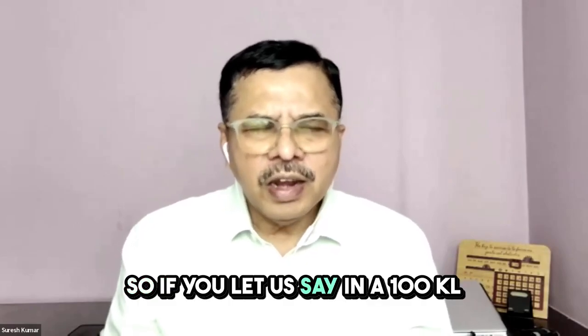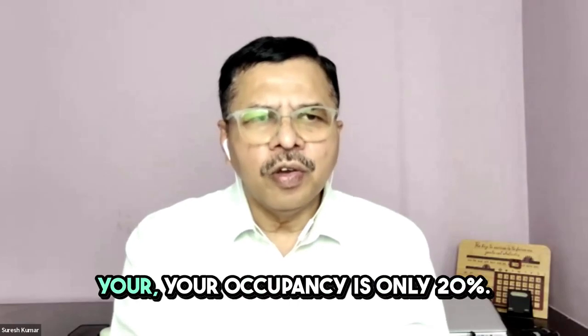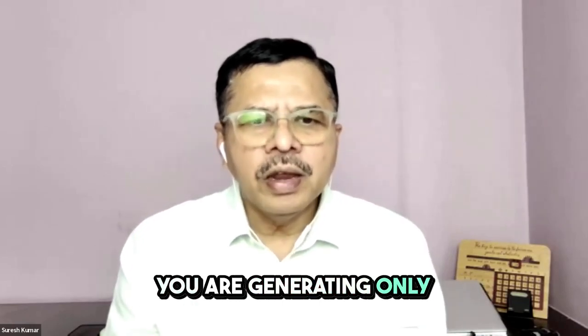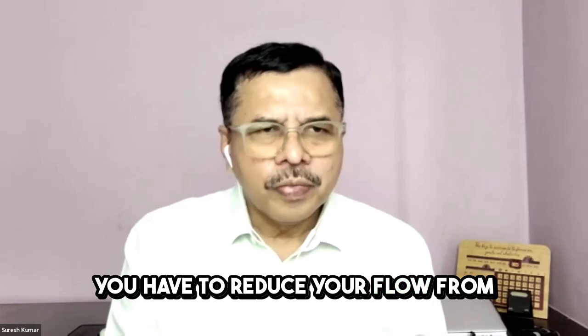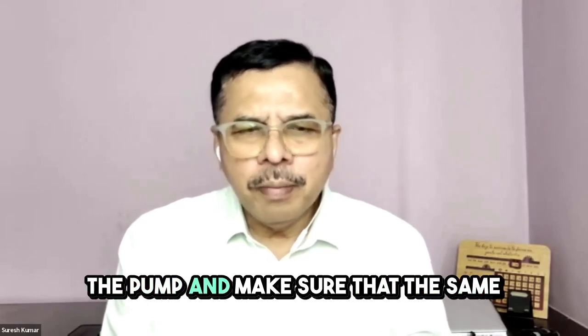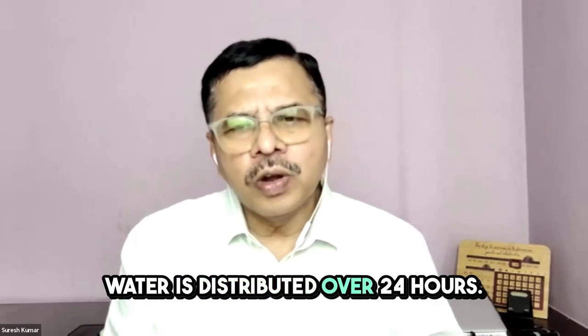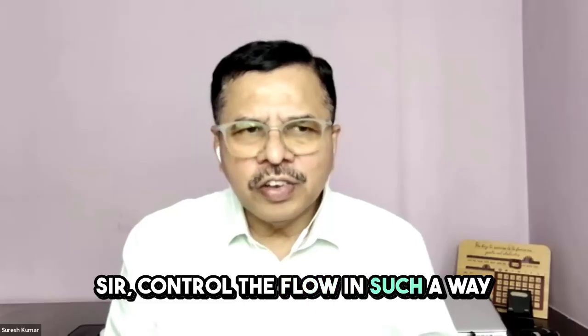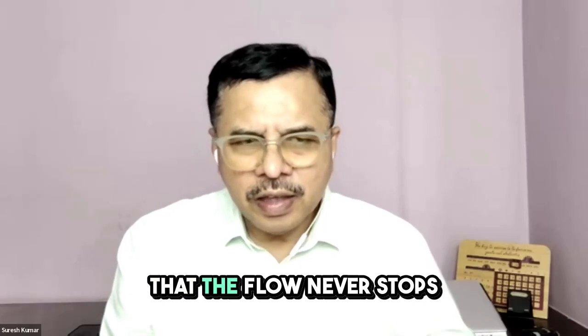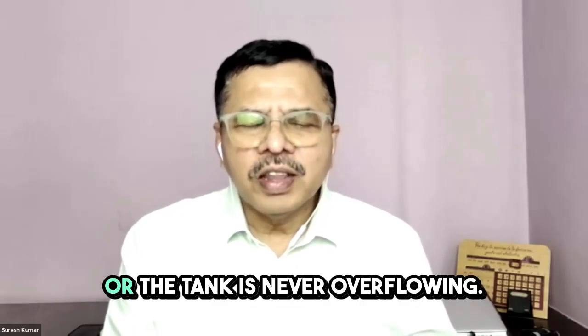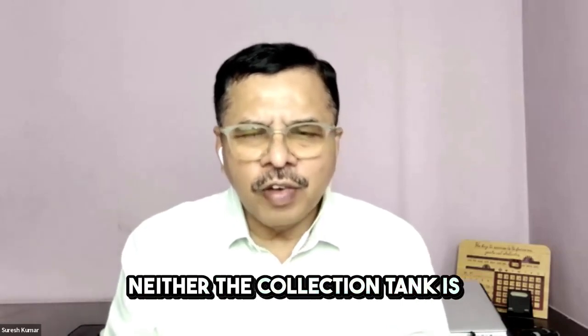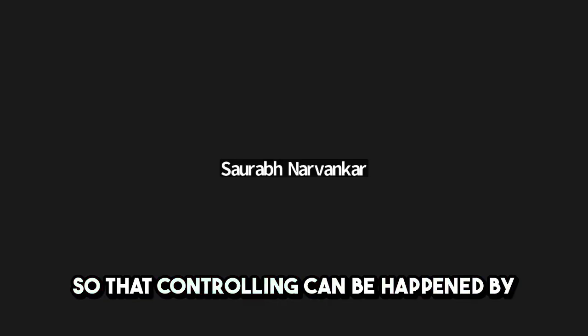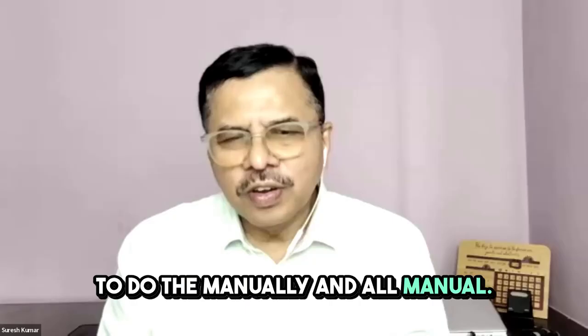Let us say in a 100 KL STP, your occupancy is only 20%, you are generating only 20 KL of water. You have to reduce your flow from the pump and make sure that the same water is distributed over 24 hours. Control the flow in such a way that the flow never stops, or the tank is never overflowing. The collection tank is neither totally empty nor totally full. Can that controlling happen automatically, or do we have to do it manually? Manual, sir.